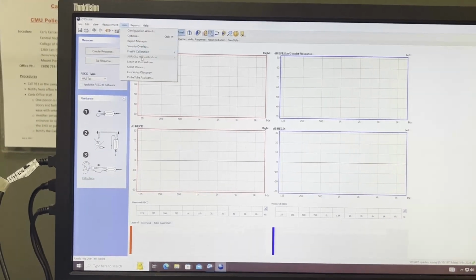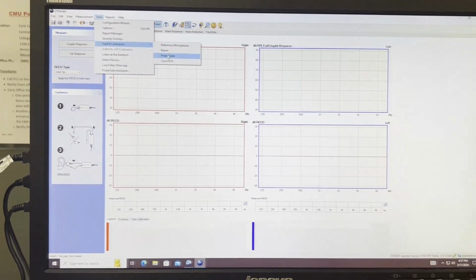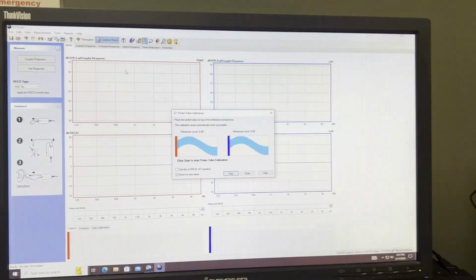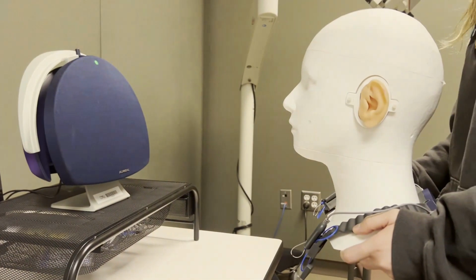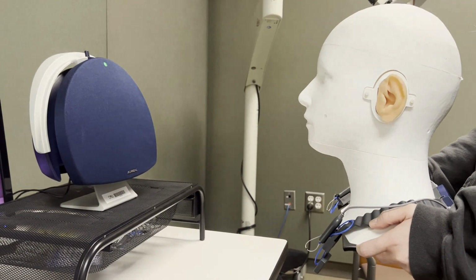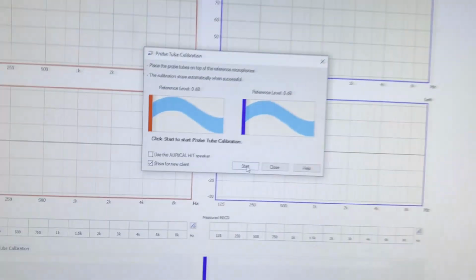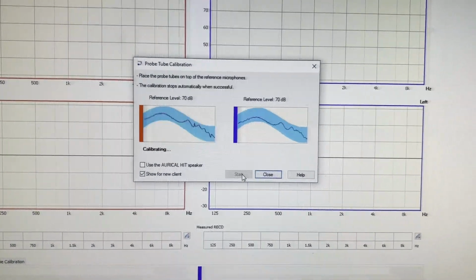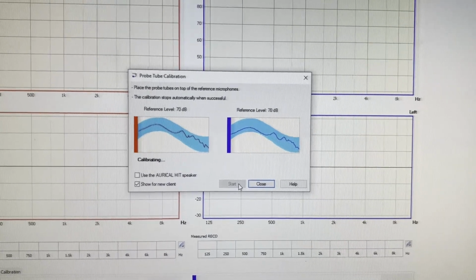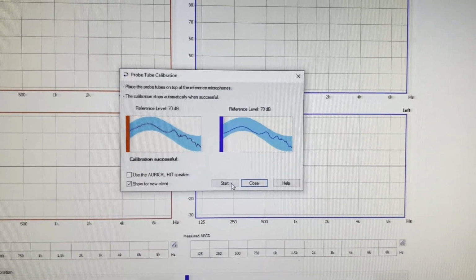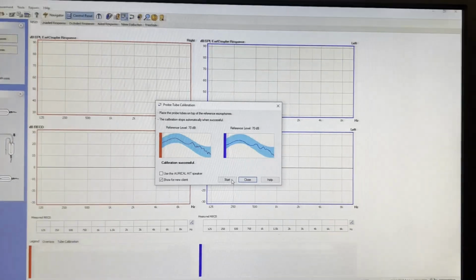So we're going to go back to tools, and we're going to hit free fit calibration, and we're going to hit probe tube, and then we're going to come over here, and the patient is 12 to 18 inches away in front of the speaker, and we're going to hit start. And our calibration was successful.